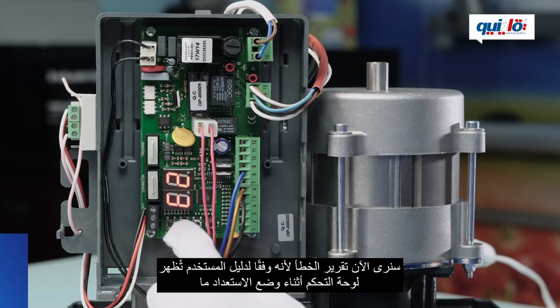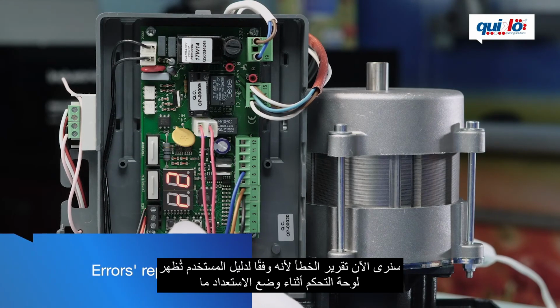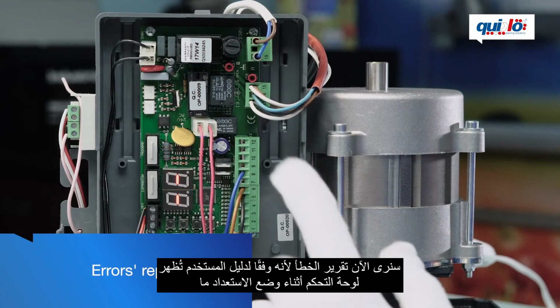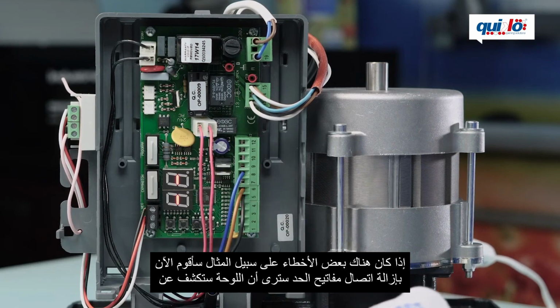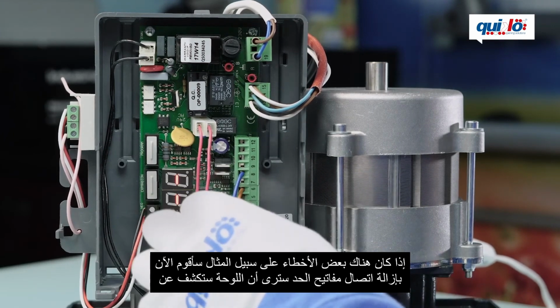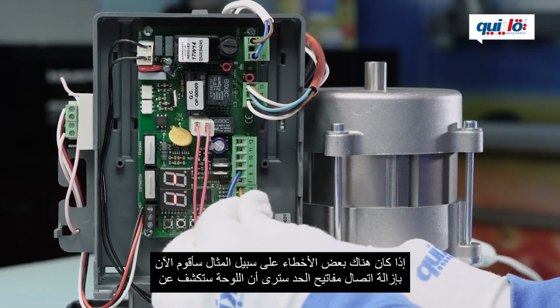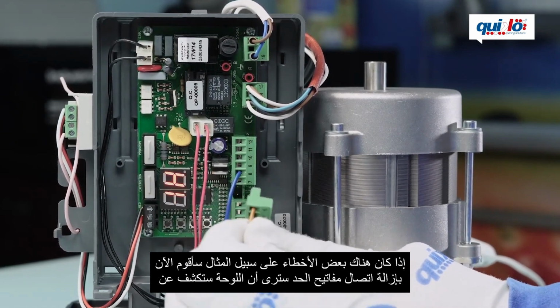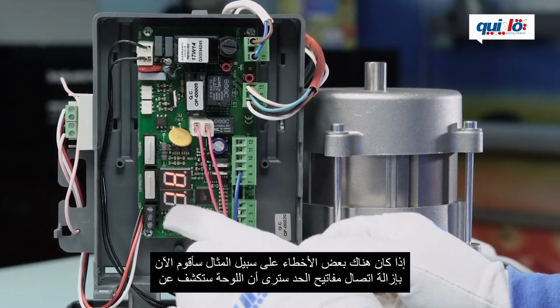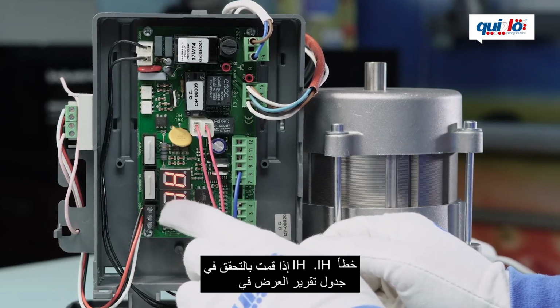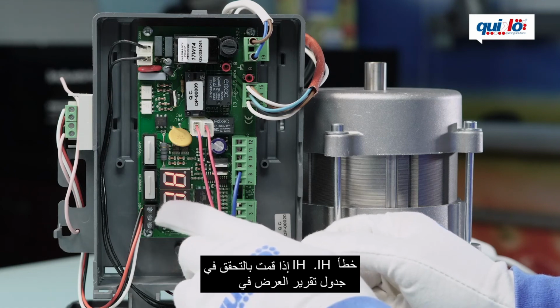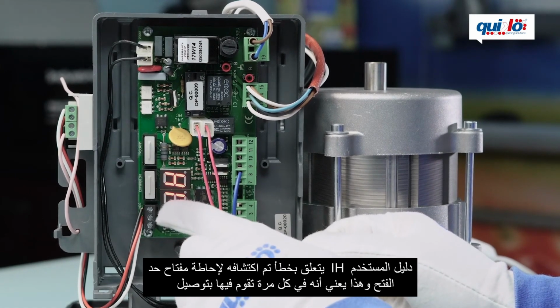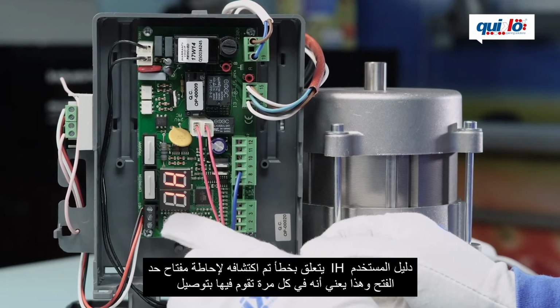We will now see the error report because as per the user manual, the control board during standby shows if there are some errors. For example, I will now remove the limit switches connection. You will see the board will detect an error, IH. If you check in the display report table of the user manual, IH is related to an error detected on the closing and opening limit switch.